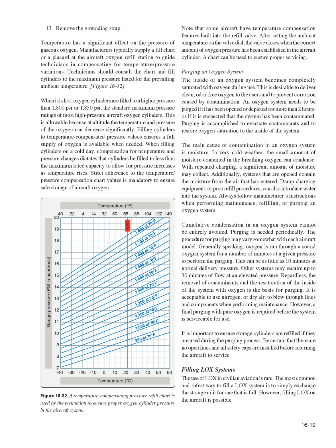It is acceptable to use nitrogen, or dry air, to blow through lines and components when performing maintenance. However, a final purging with pure oxygen is required before the system is serviceable for use. It is important to ensure storage cylinders are refilled if they are used during the purging process. Be certain that there are no open lines and all safety caps are installed before returning the aircraft to service.